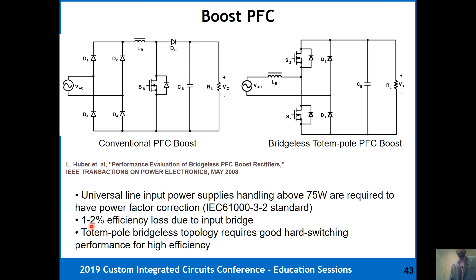With the introduction of GaN, you can completely eliminate this bridge, giving you something called a bridgeless totem pole boost. That gives a 1 to 2% efficiency improvement because you got rid of the bridge. The ability to hard switch without reverse recovery charge is what makes this converter possible, pushing a 96-97% efficiency converter up to 98-99%. Every percentage matters, because these converters go into data centers and the millions of racks available there. Every percentage leads to lower thermal losses and lower cooling requirements for data centers, which is why these things are highly important.